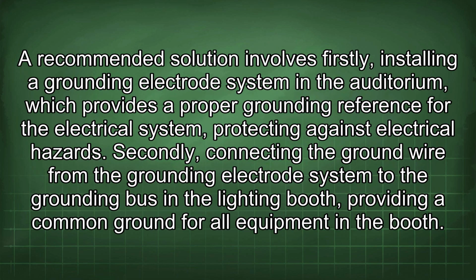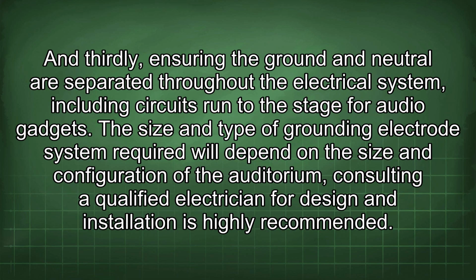A recommended solution involves, firstly, installing a grounding electrode system in the auditorium, which provides a proper grounding reference for the electrical system, protecting against electrical hazards. Secondly, connecting the ground wire from the grounding electrode system to the grounding bus in the lighting booth, providing a common ground for all equipment in the booth. And thirdly, ensuring the ground and neutral are separated throughout the electrical system, including circuits run to the stage for audio gadgets.